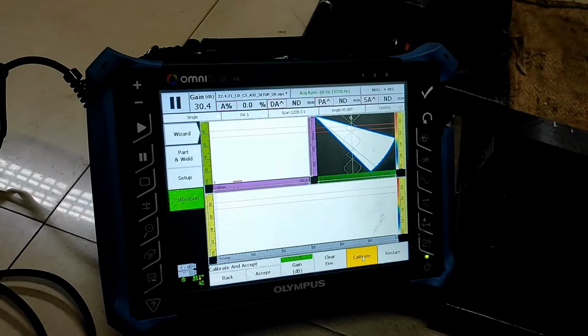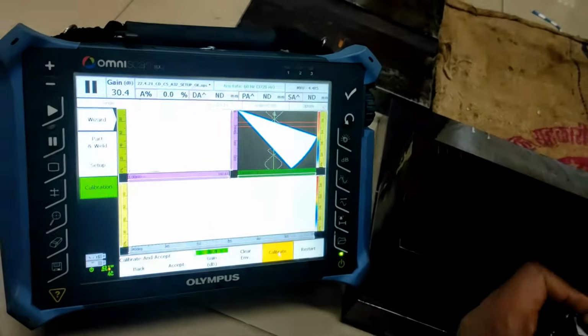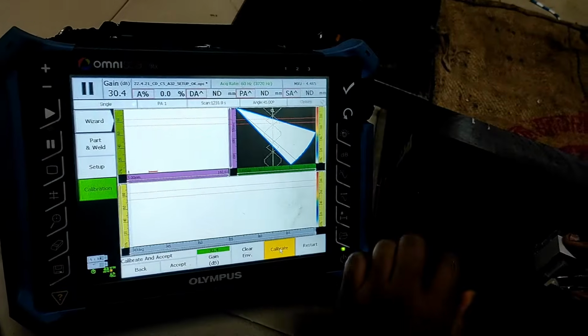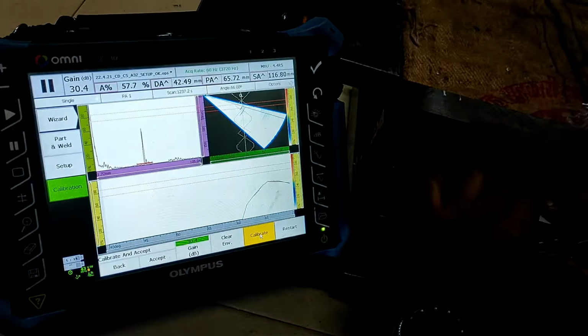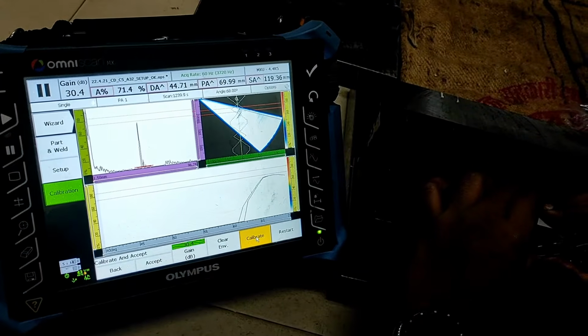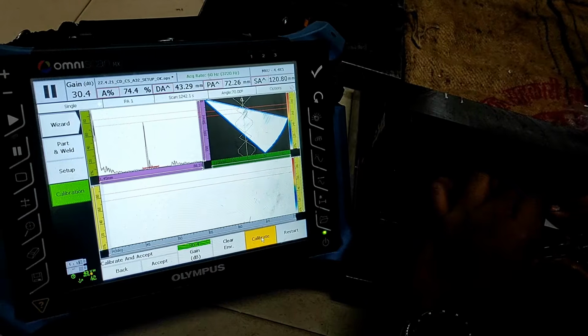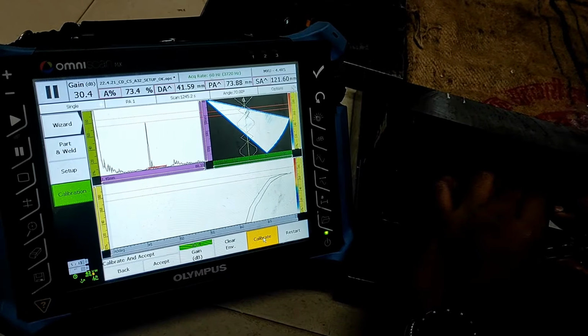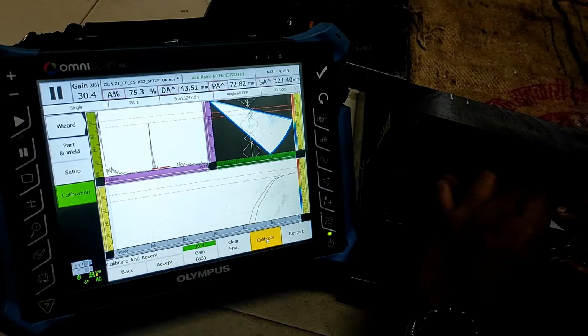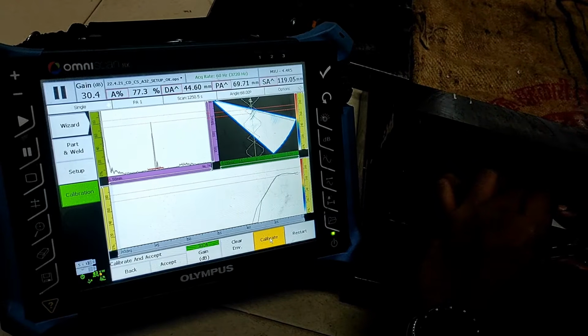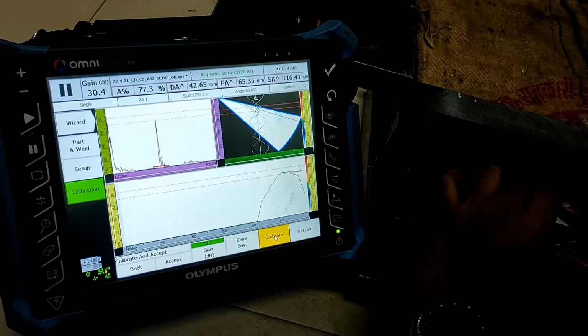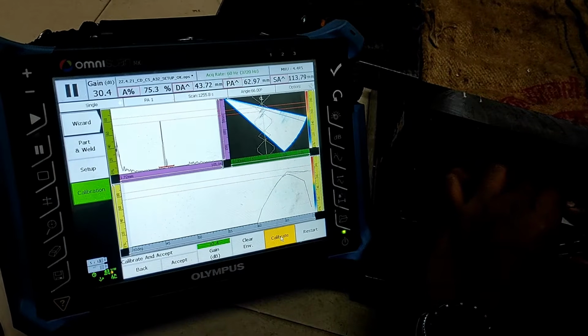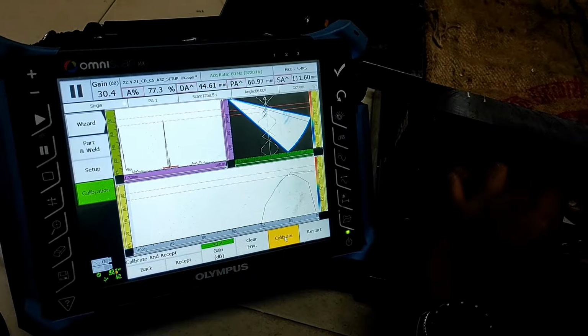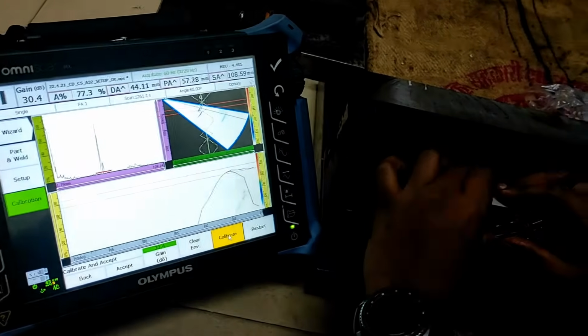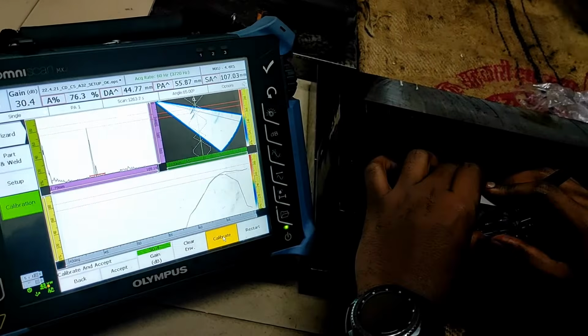Actually we done the calibration. Now we are going to take the amplitude in the envelope. This is the final actually in the sensitivity setting. Just we have to take all the amplitudes inside the envelope. That's the final in sensitivity setting, sensitivity calibration. Just we have to move very slowly.